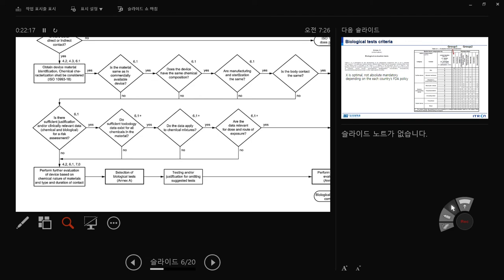Do the data apply to chemical mixtures? You can combine two chemicals together and investigate each individually — chemical A and chemical B — but you need to ask: what happens when you combine them? This kind of complex mixture should also be evaluated. Are the data relevant for dose and route of exposure? If your material is for IV injection, but you only evaluated subcutaneous interaction and never evaluated blood interaction, that's not consistent with the real clinical setting. Always think about how you deliver your material: IV, oral route, direct implantation, local or systemic distribution.